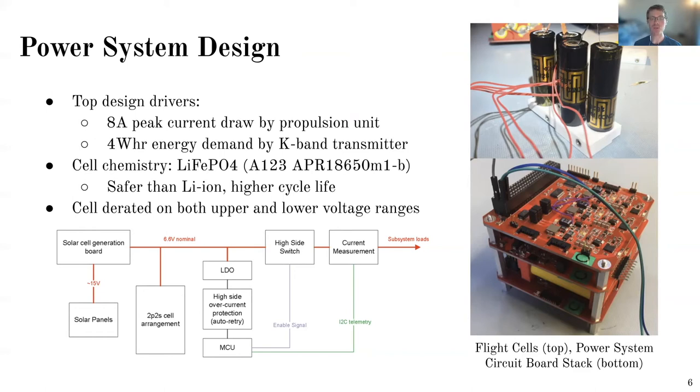And then their cycle life is higher just off the shelf, so before any derating. So once we did get this cell, we did additionally derate it. So we took the upper bound voltage. So the specified upper bound voltage was 3.6 volts, and the lower bound was around 2 volts. So we essentially brought both those ranges in to give us a little headroom on the bottom, so we're never going to 100% depth of discharge. And then the upper end is lowered as well, and that increases the cycle life.